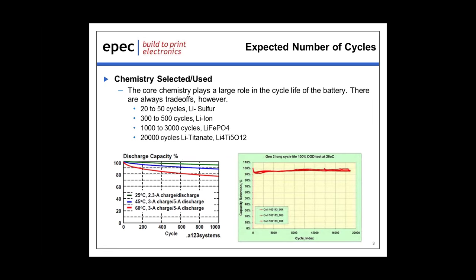And then if you look at the other chemistry below that, lithium iron phosphate, that particular chemistry you get a lot better cycle life. It shows about 1,000 to 3,000 cycles. With that particular chemistry, you're giving up volume - it's going to be a larger cell, a little heavier cell. So right away one of the trade-offs is you're going to get a little larger battery, but in exchange you might get cycle life. And where this really could come in handy is sometimes some of our customers have batteries that are very very difficult to replace. For instance, there could be an installation on top of a mountain, and where it costs a lot of money, thousands of dollars to get a team up there to swap out batteries. These are type of chemistries that are really handy. Obviously they're handy in portable electronics as well, but when you start looking at extremes and the cost of service, those are factors that you look at when selecting the chemistry.